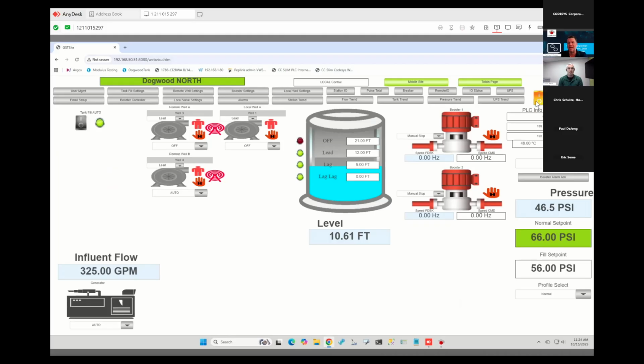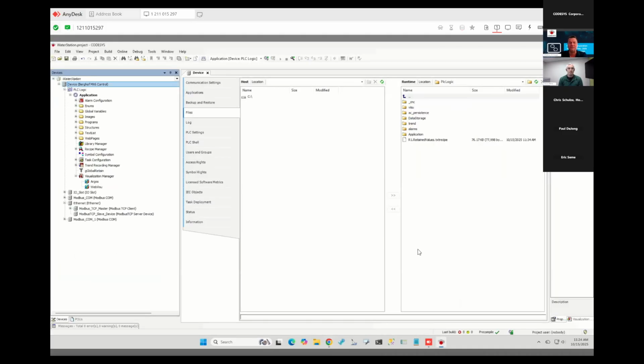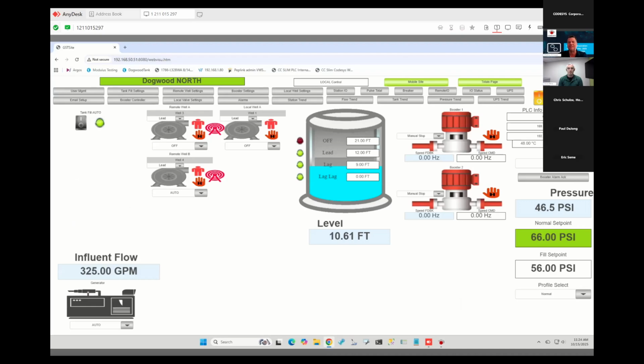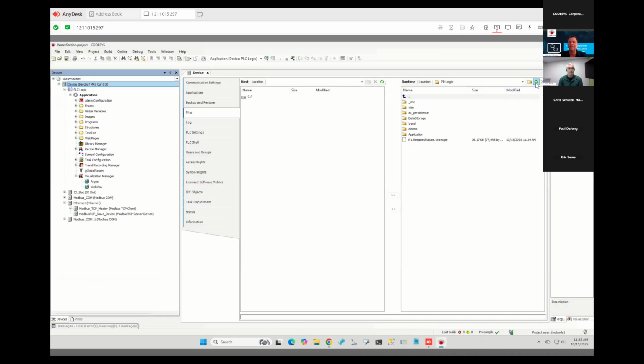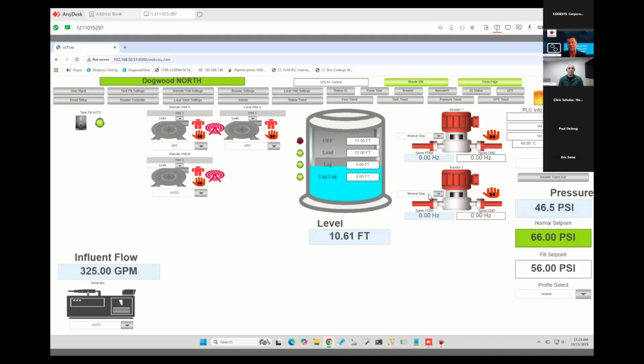So if everybody can see that, right now my timestamp on my file is 11:34. If I hit save settings, what now has happened is 1:14 is my timestamp. What have we just done? We've just configured a pump station, created a recipe for that pump station, and backed it up and saved it. Now, this can be offloaded from the PLC to that same USB stick so that when the customer restores, he's able to bring that station completely back up. Or if he does have one that is close to that station, he's able to restore that to start without having to go through and do a ton of the configuration like I just showed you.